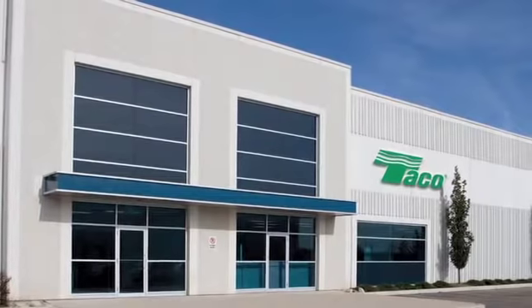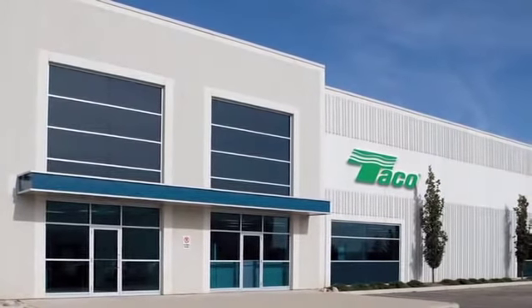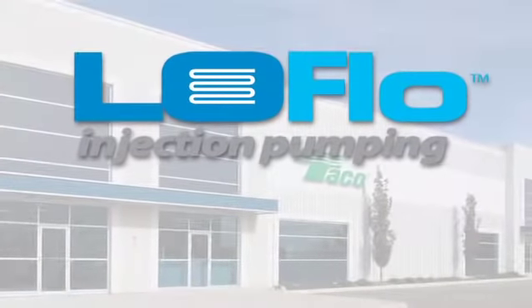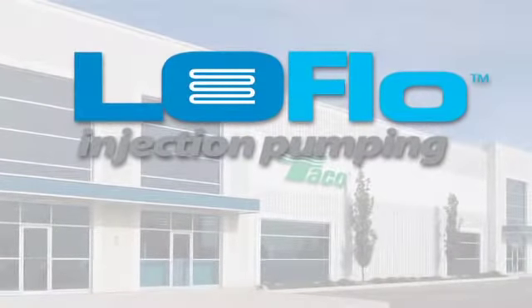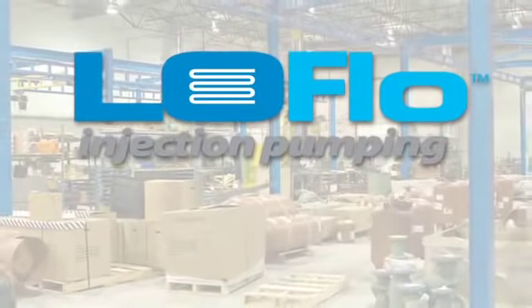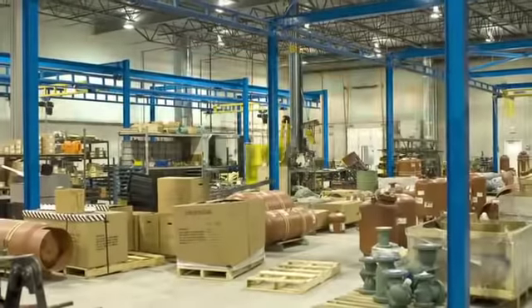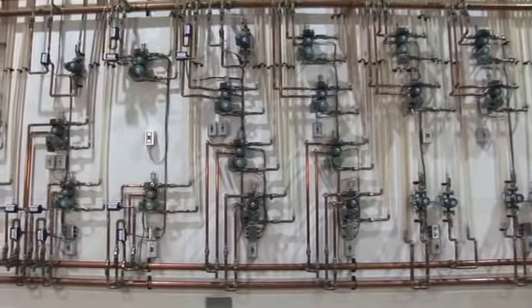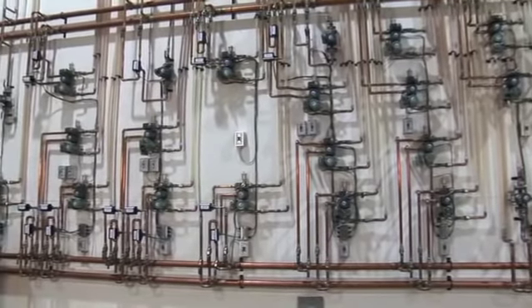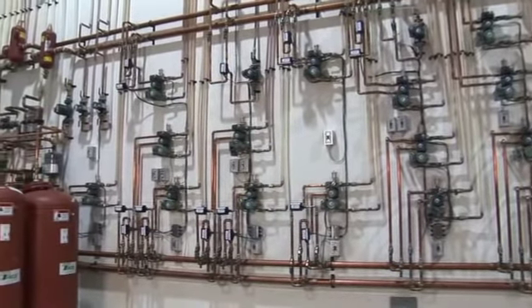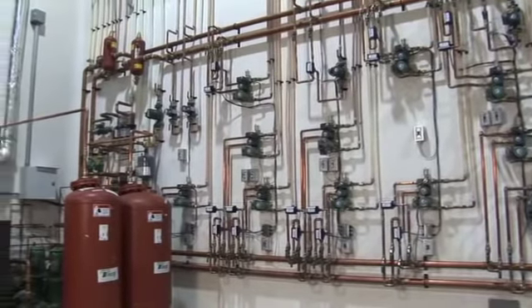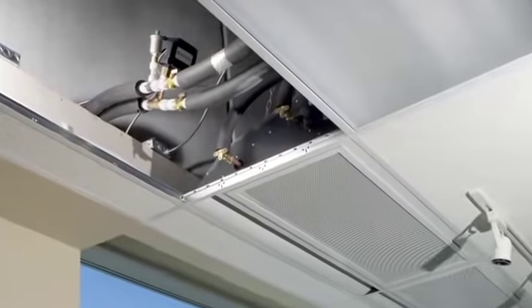TACO's new Canadian headquarters in Milton, Ontario, comes equipped with a prototype of a new radiant cooling system called LoFlo. The TACO LoFlo radiant cooling system supplies both cooling and heating for the building's 30,000 square foot interior. This unique system employs TACO load-match circulators to deliver heating and cooling energy to a variety of terminal units, including chilled ceiling panels, active and passive chilled beams, fan coils, and heat pumps, all in the same piping distribution system, despite each of the terminal units requiring different temperatures.